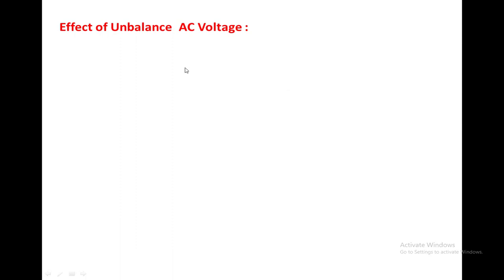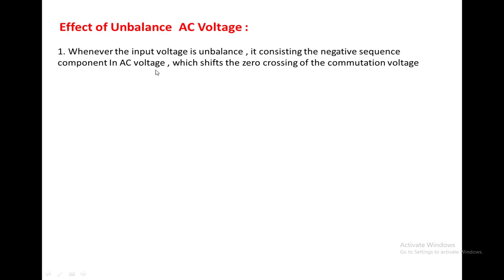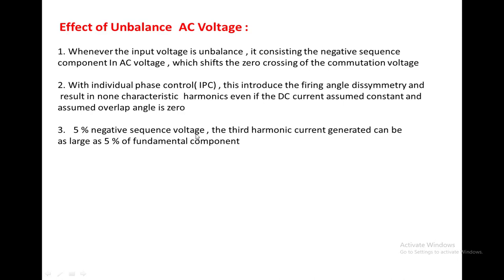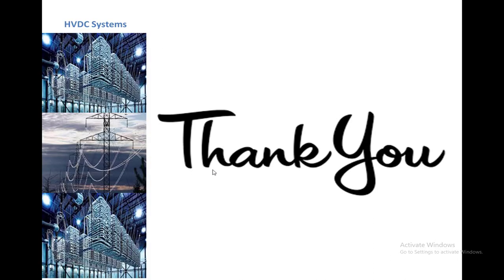Regarding the effect of unbalanced AC voltage: AC voltage feeds power to the two converters at the sending end through the transformer. If there is an imbalance in AC voltage — a change in voltage from phase A to phase B or phase B to phase C, or a change in angle — then the voltage contains a negative sequence component that shifts the zero crossing of the commutating voltage of a device with individual phase control. This introduces firing angle dissymmetry and results in non-characteristic harmonics. Even if the DC current is constant and the overlap angle is assumed zero, five percent negative sequence voltage can generate third harmonic current as large as five percent of the fundamental component. Thank you — in this class we have discussed non-characteristic harmonics and how they are generated in an HVDC system.